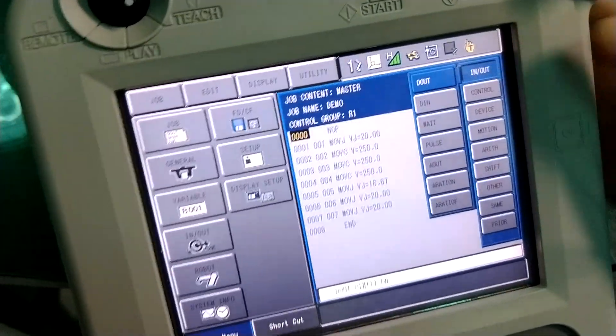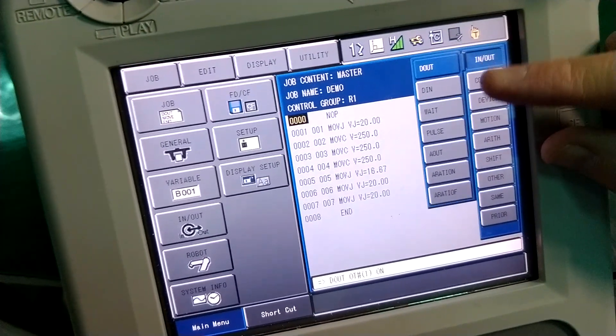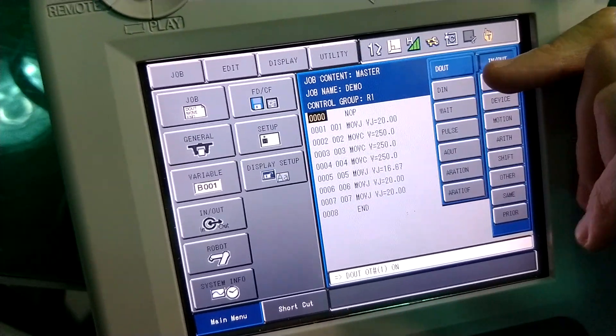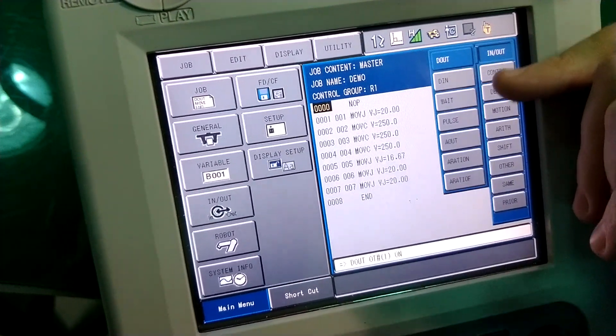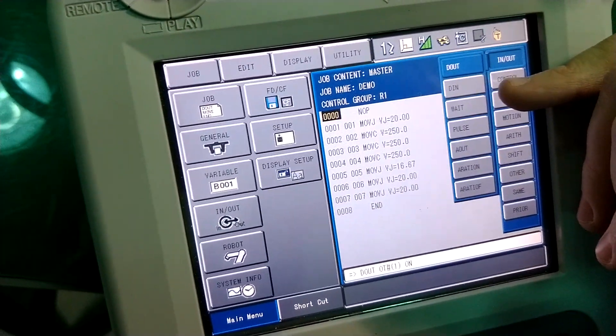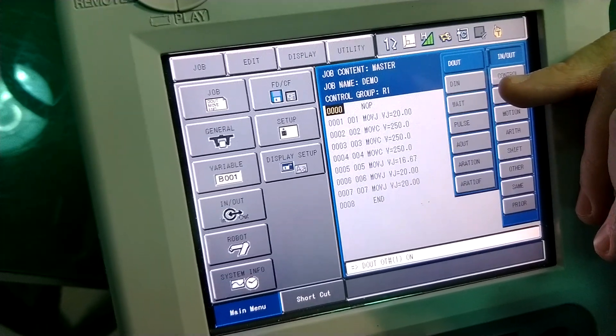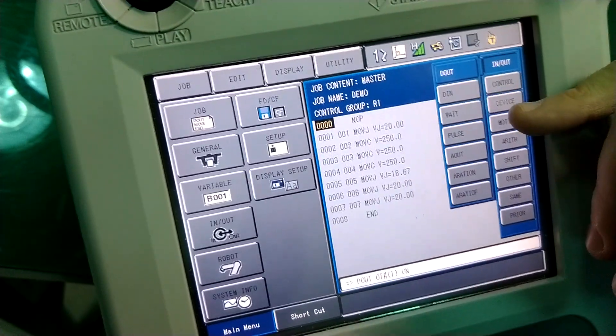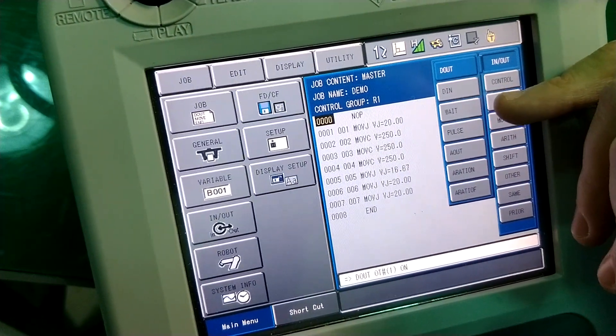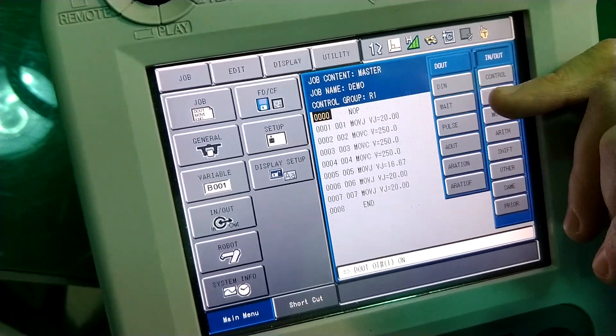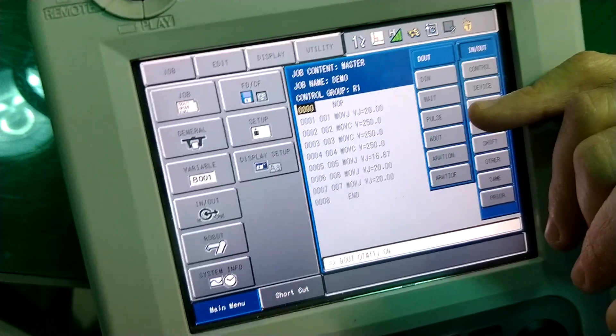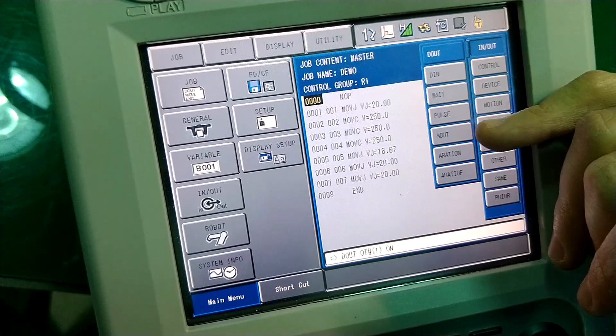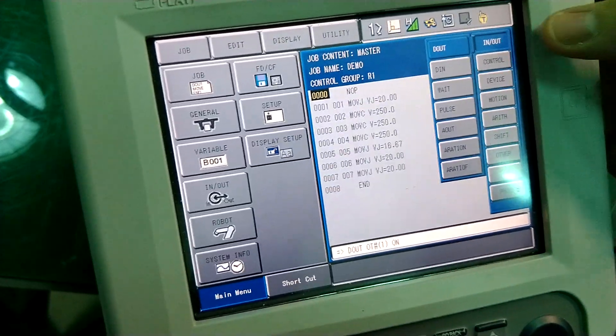In and out would be digital inputs and outputs. So if I want to turn on a digital output, I use a DOUT command. If I want to do something with a digital input, I use a DIN. If I want to wait for an input, I can do that. I can pulse an output, and this is analog output right here.